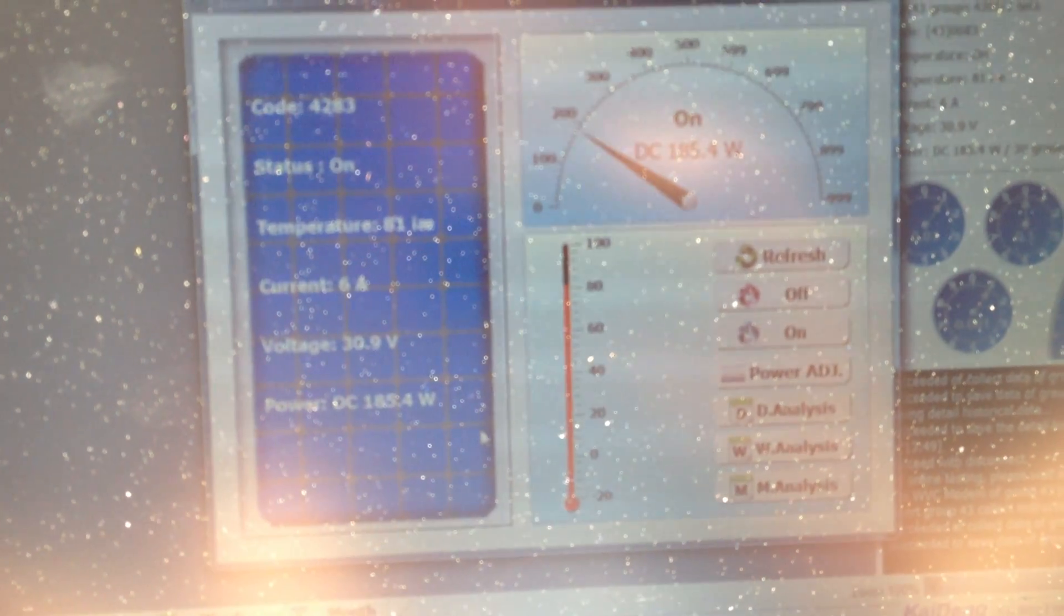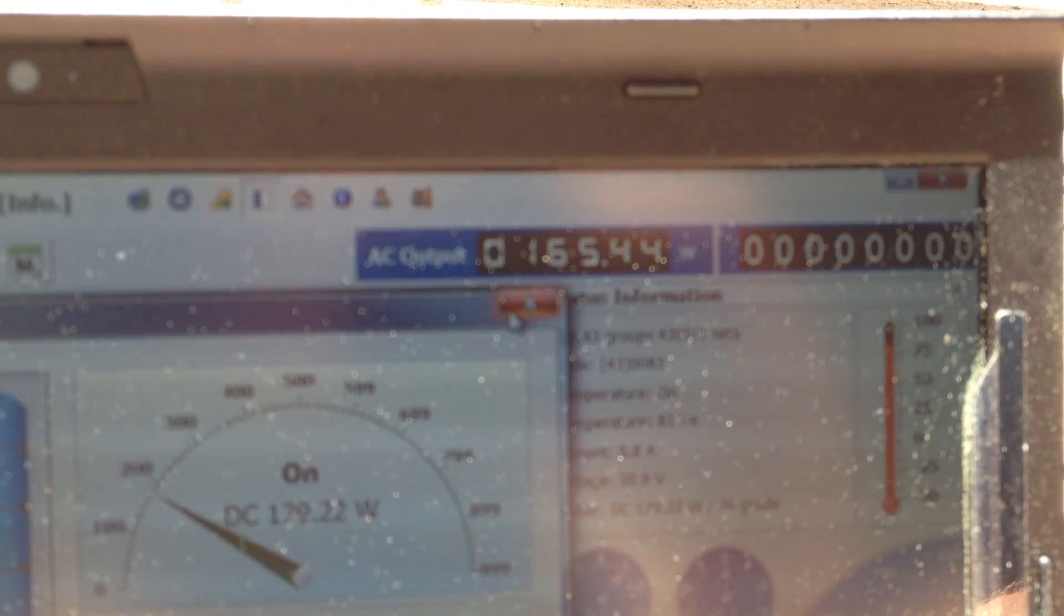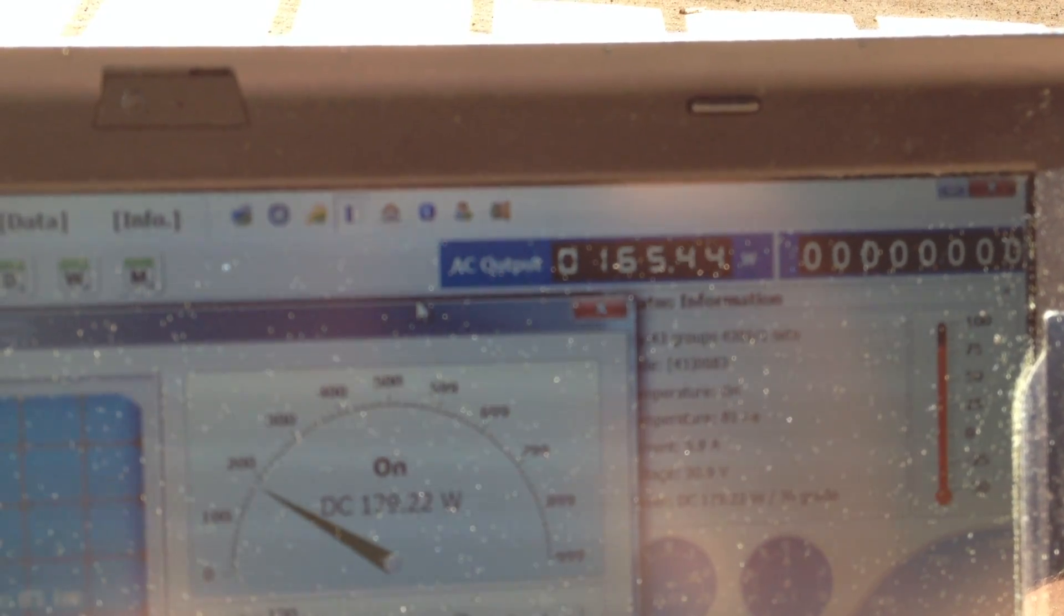If I double click on it, I see several performance data including the actual power, the DC power, which in this case at the moment is 177 watt. Over here you see the AC output which is supposed to be 168, so roughly 10 watt loss between the DC and AC conversion.